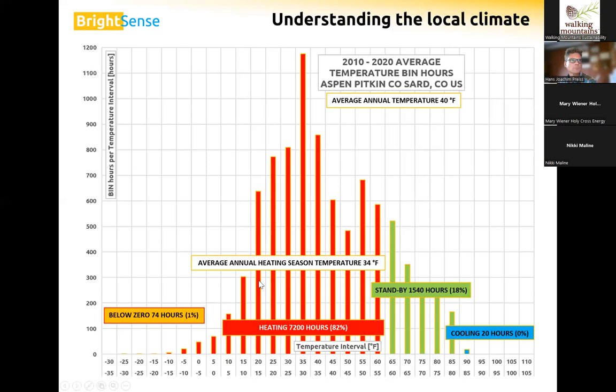We have a few hours below zero, and we have a few hours where we might need cooling. And then we have quite a few hours that are really nice, where we don't need heating or cooling, really nice ambient temperatures. Looking at this, there's a very small number of hours below negative 15, just a handful. So I would argue that the heat pump with the performance that we were discussing earlier is a perfect match for this type of climate, because the majority of the time it would work extremely well at really nice COPs.